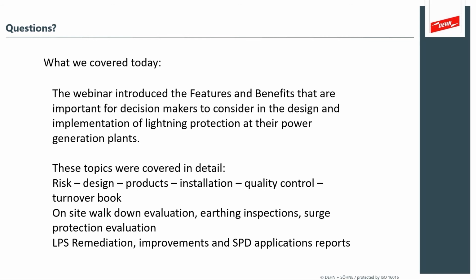The clamp-on just measures loops, and you can't use it for that purpose unless you're going to be doing it for overhead power lines or so. You can use these clamp-ons for those types of measurements of individual earth rods in overhead power lines, but not really in a power generation facility in that way.